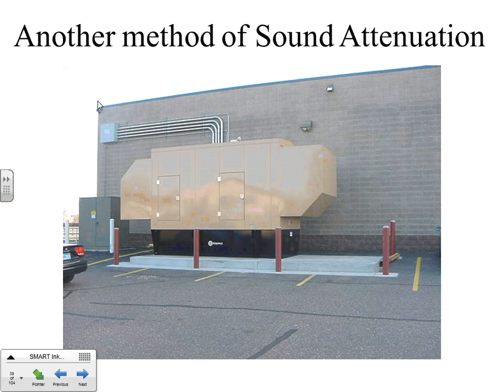Here's a little different design. This is a Target store again. In this one, we're turning the inlet air as well. The inlet comes through here, across the generator inside, baffled out, and moves up. So those are the only louvers. It makes for a very clean design at the site, and a dual contained tank.